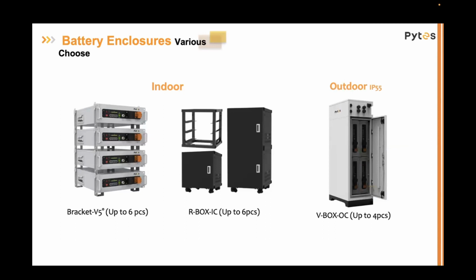Now here are some of our enclosures for the V5 we're really excited about. We have our standard rack mount, very similar to our other batteries - we can stack up to 6 of these together. Like I mentioned earlier, we can run the bus bar up to 300 amps maximum, allowing us to directly hook into a Sol-Ark 15K unit. That rack mount unit is, of course, indoor rated only - we don't want to put those outside. We want to keep those in a nice, safe area, ideally next to the inverter system.